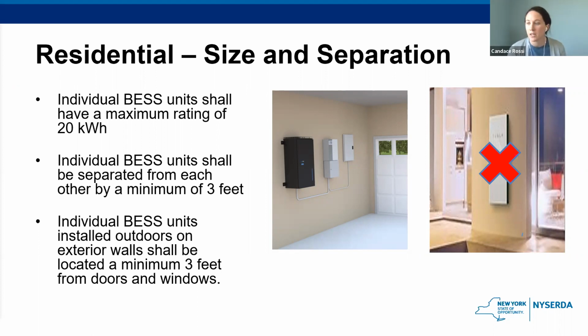Also, individual battery energy storage units shall be separated from each other by at least 3 feet. And individual units installed outdoors on exterior walls shall be located a minimum of 3 feet from doors and windows. Also, you are unable to install these projects within living spaces. While the image on the left shows it properly installed in a garage, the one on the right shows an installation in a living room, which is not allowable by the code.